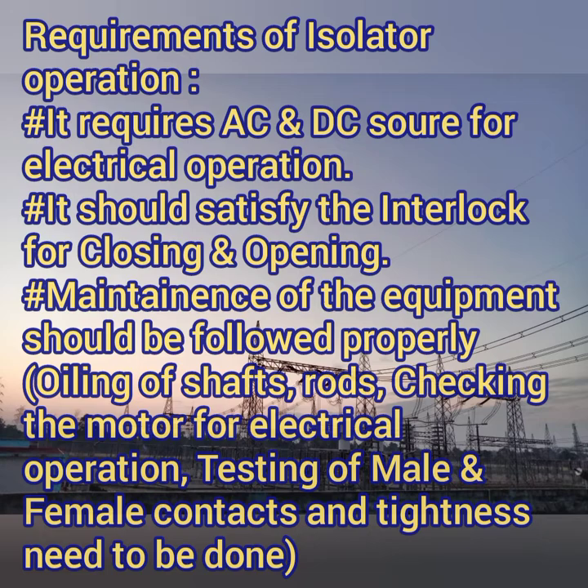Isolators need to be maintained properly, and a yearly shutdown is recommended. Because isolators are mostly kept in open areas, they can be damaged by external moisture, lightning, and other environmental factors. Maintenance includes contact resistance measurement (CRM) between the male and female contacts, cleaning and oiling the rotating shafts to prevent damage from reduced lubrication, and checking the tightness of shafts and connecting portions.